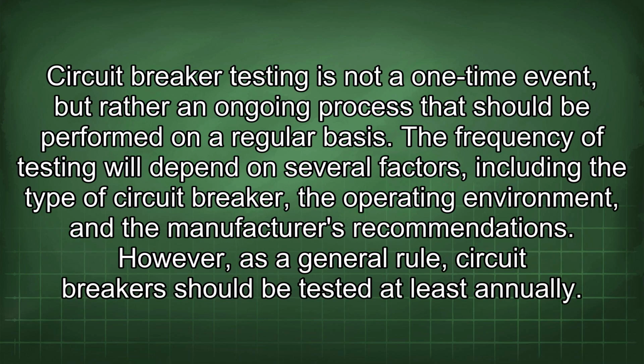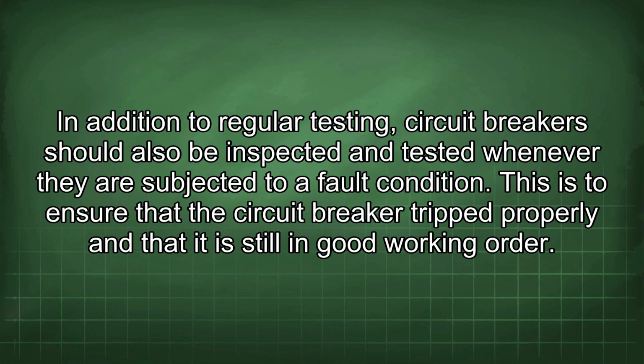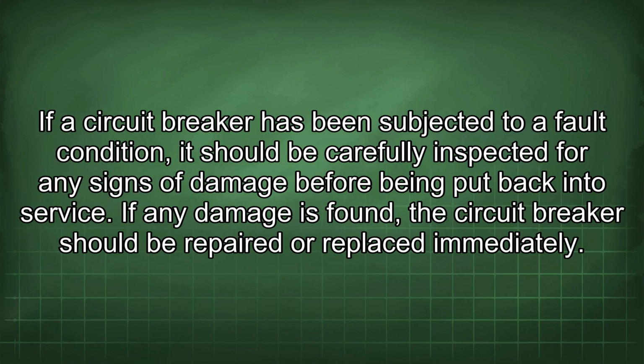Circuit breaker testing is not a one-time event, but rather an ongoing process that should be performed on a regular basis. The frequency of testing will depend on several factors, including the type of circuit breaker, the operating environment, and the manufacturer's recommendations. However, as a general rule, circuit breakers should be tested at least annually. In addition to regular testing, circuit breakers should also be inspected and tested whenever they are subjected to a fault condition. This is to ensure that the circuit breaker tripped properly and that it is still in good working order. If a circuit breaker has been subjected to a fault condition, it should be carefully inspected for any signs of damage before being put back into service. If any damage is found, the circuit breaker should be repaired or replaced immediately.